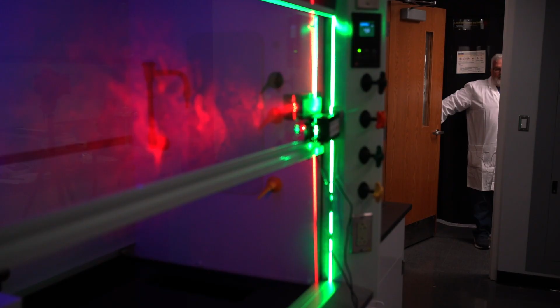The other one that we don't have a good example of is when you have multiple hoods in a room. We like to leave the hood we're testing full open and then go to the other hoods and open and close them. Particularly in the VAV system, that's going to change that. You're going to have lag time issues. You have a lot of different issues. So again, these are real world challenges. These are things that people do every day. And so it's not a static ejector sitting in a certain place or whatever.